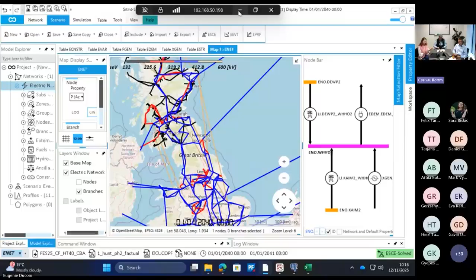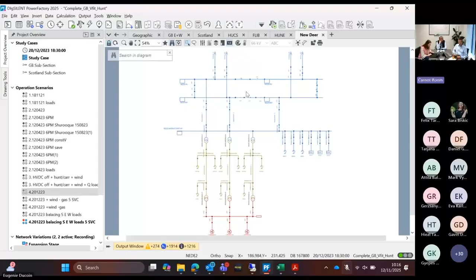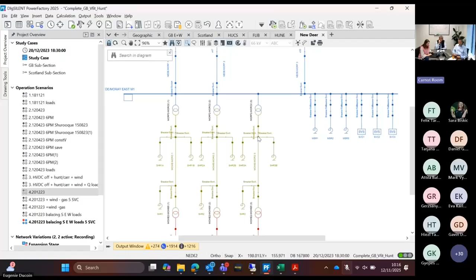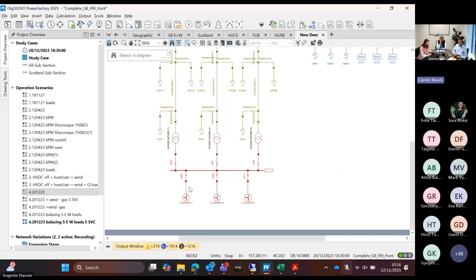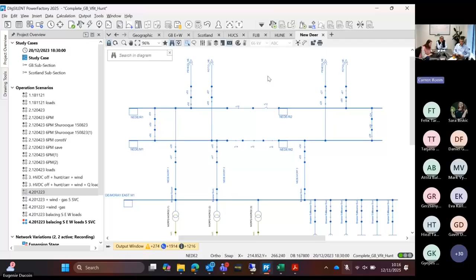So we built a second model with all of the lines, substations, etc., the same as the other model, shown here, except that in this one, we also have substation configurations. So for example, here in New Deer, we have modeled the transformers that go down to lower voltage levels. We have reactive compensation, we have every single unit of generation modeled, SVCs, reactors, etc.